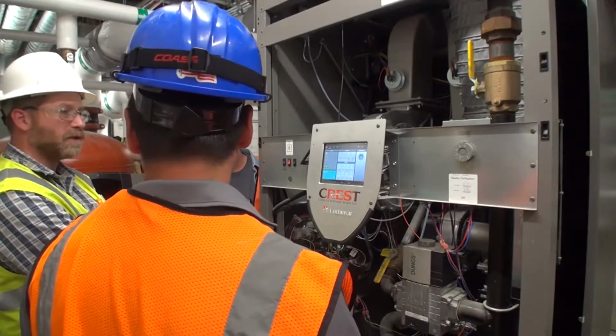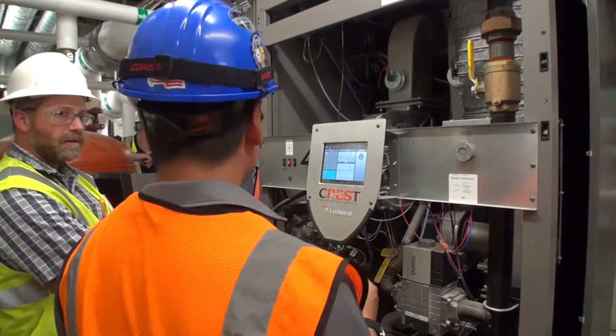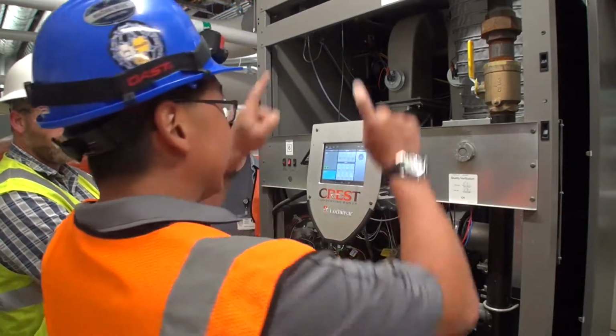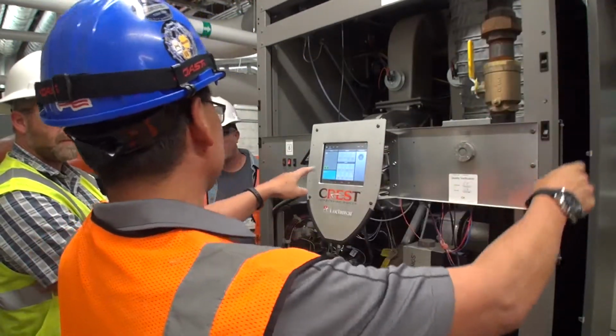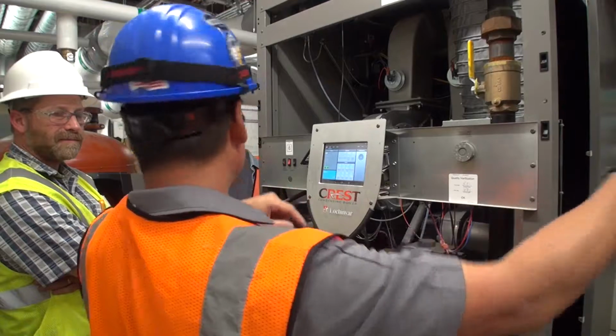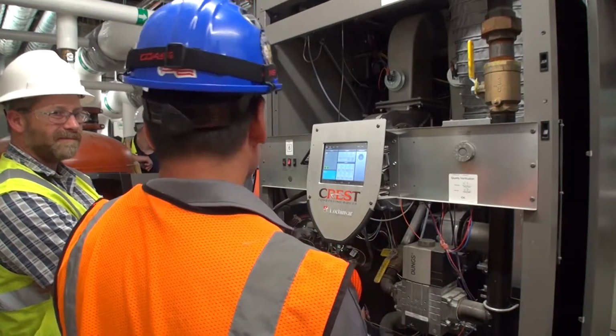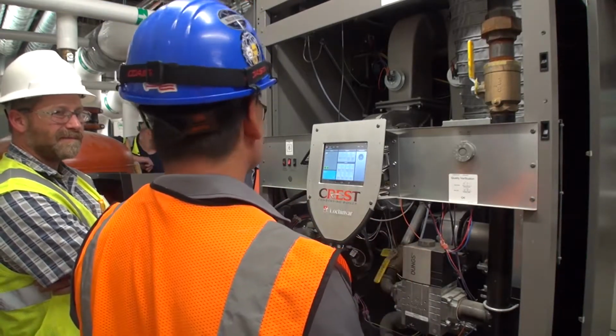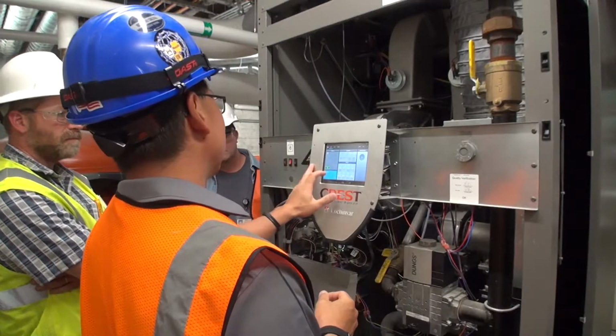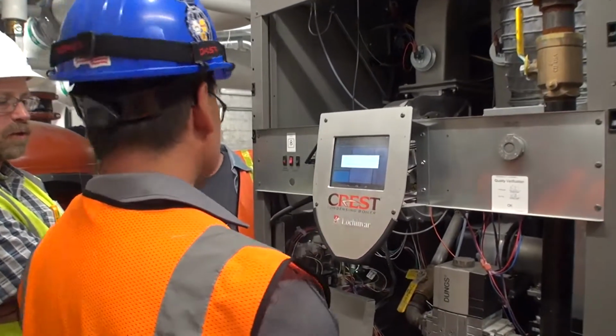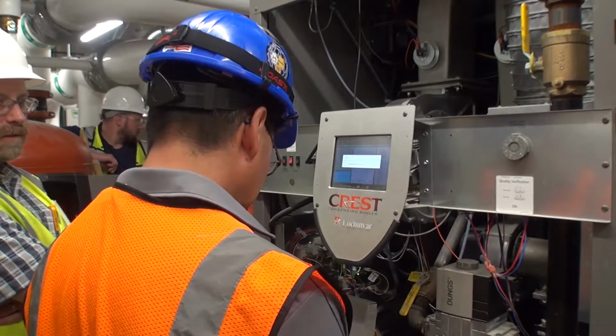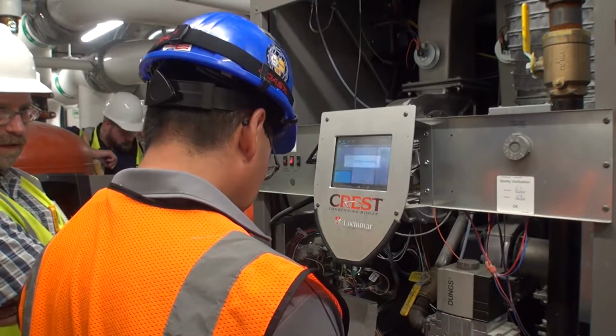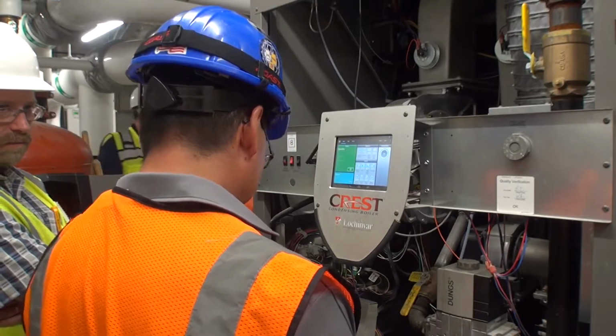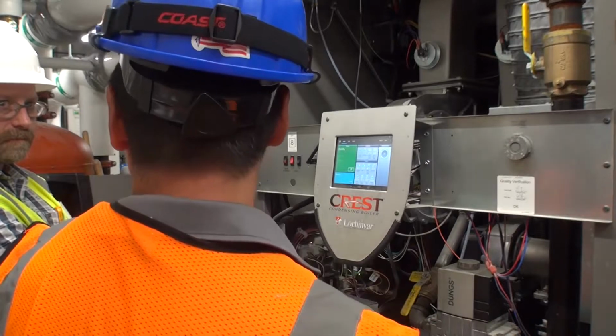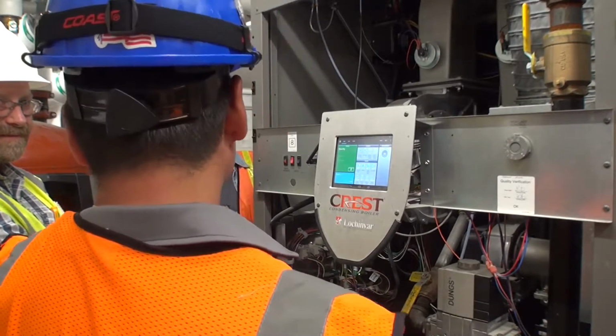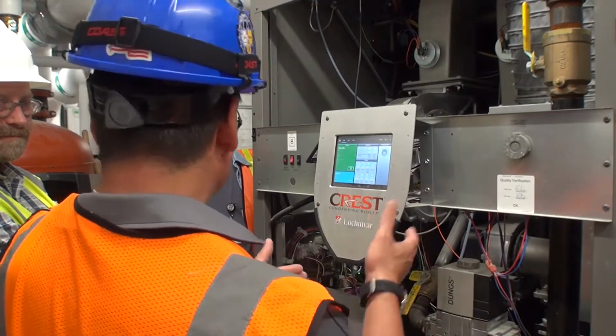Okay. So it was pushing water into the boiler. Yeah, and those two valves are closed because someone had put one off and turned the other one completely off. So again, you want to keep them on. So if they had set those pumps up to go off on the off switch of the boilers and interlock it with the boilers. But no one would do that because that's not a code. Typically what you do is you put the pumps after the boilers.